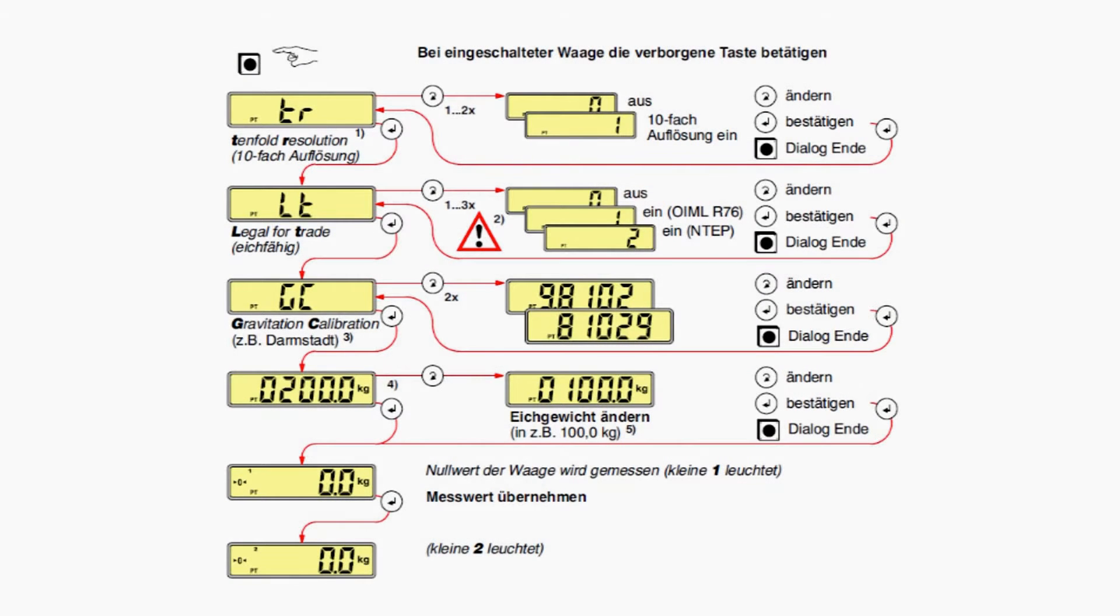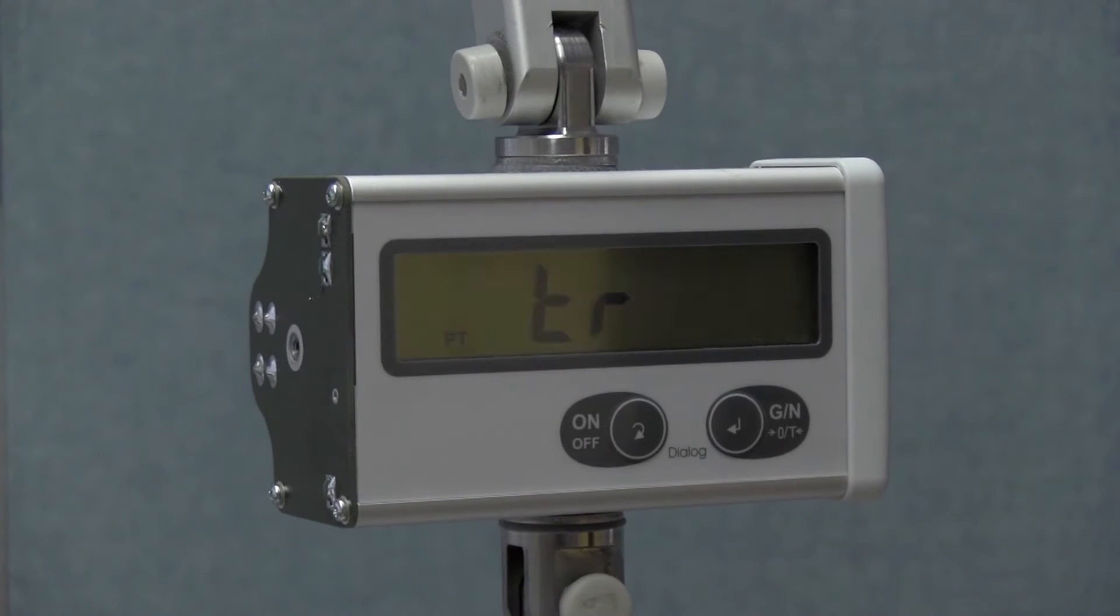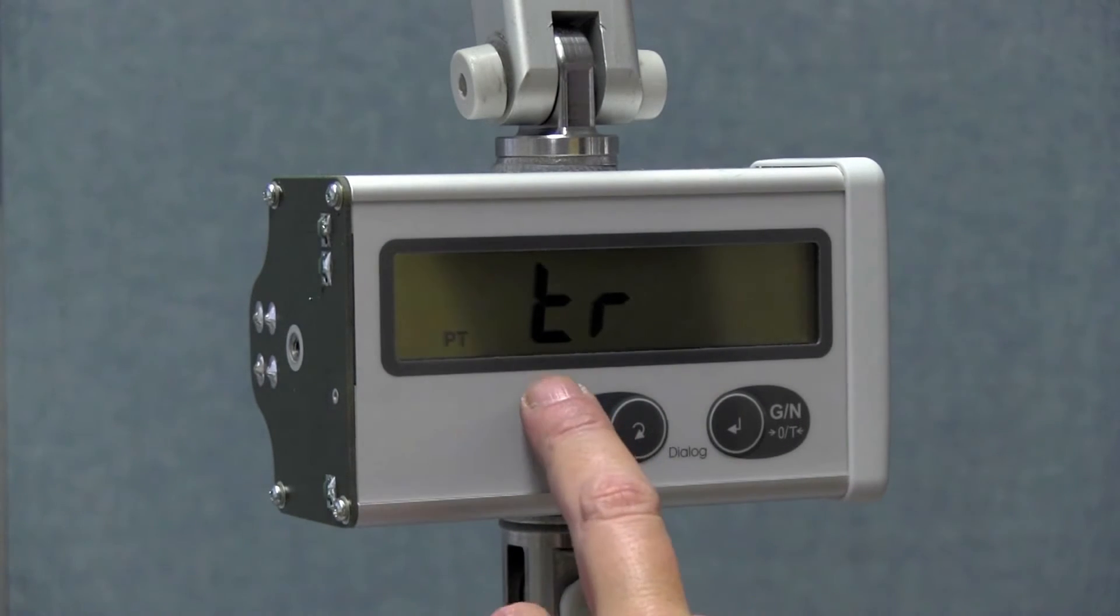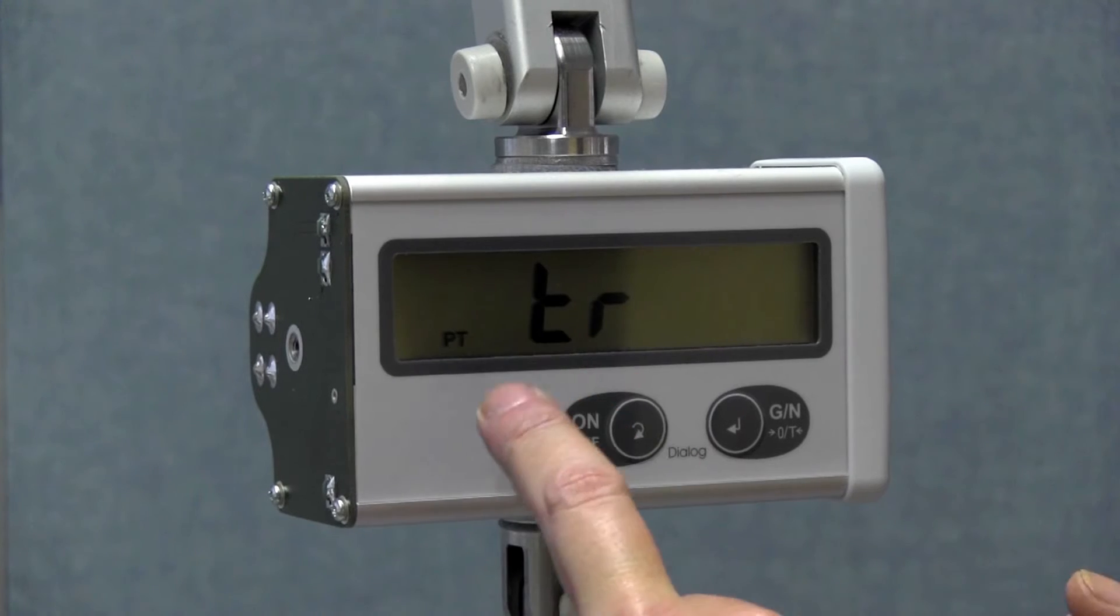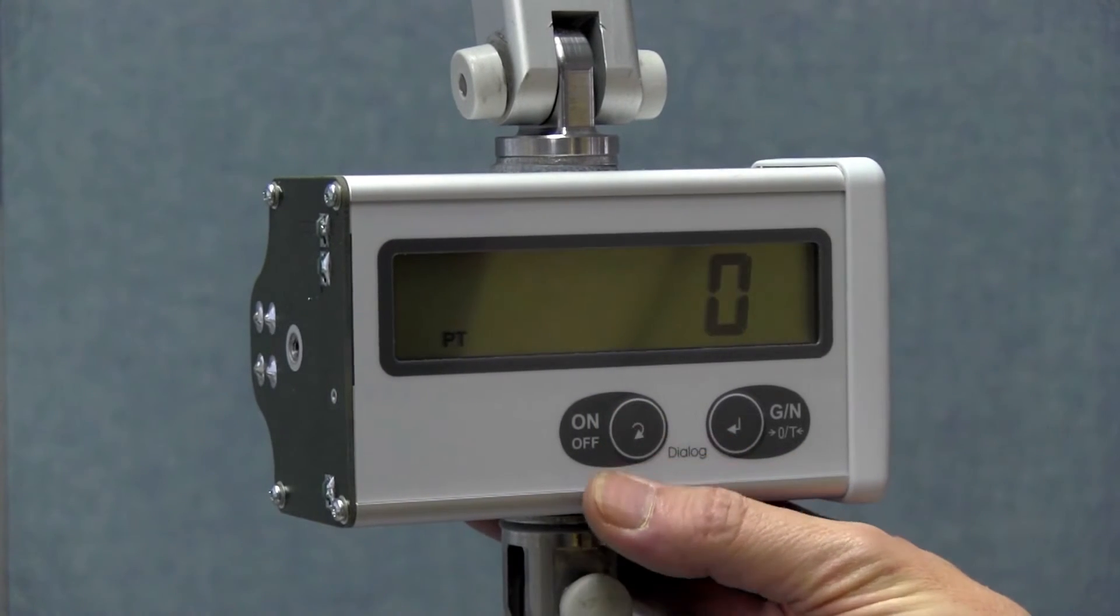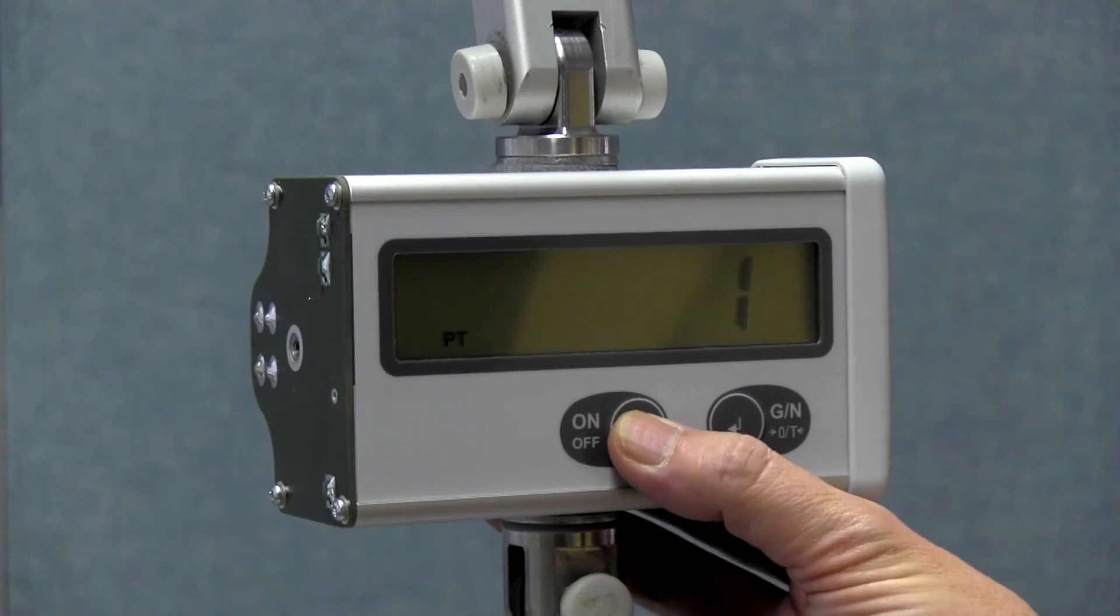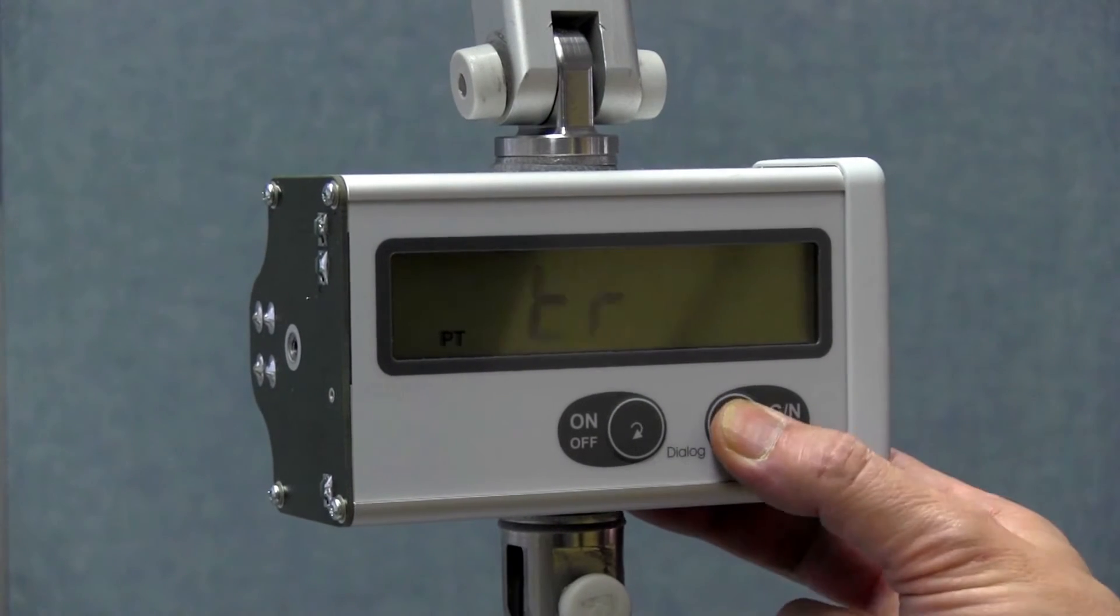Now I press the hidden button to go to the setup parameters menu, and the first query criterion is tenfold resolution. The setting of the resolution in the display, one or two places after the decimal. I can either turn it on or off, zero is turned off, and one is turned on. I set one in this case.